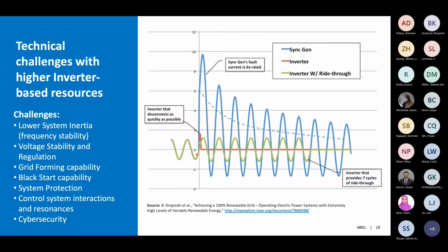But with inverter-based grids, even if you were to implement the same type of fault, you can get a variety of responses. You can get this really fast response shown in red, where it sees the fault and disconnects very quickly and goes to zero. Or you could ride through the fault and you would get this green characteristic. Maybe it rides through for 7 cycles and then trips off. But in either of these cases, they don't look like this blue graph.